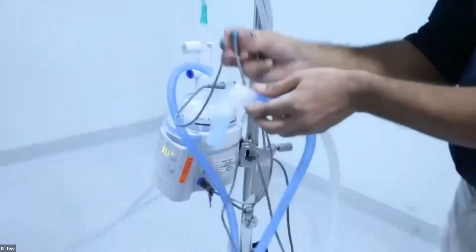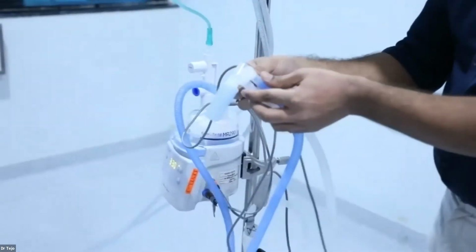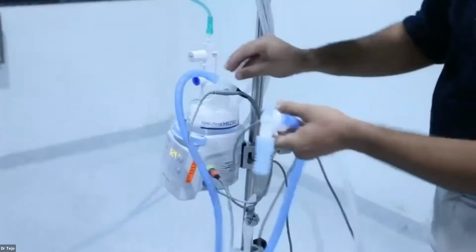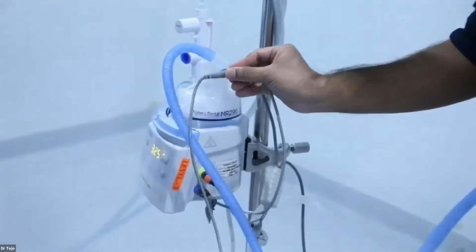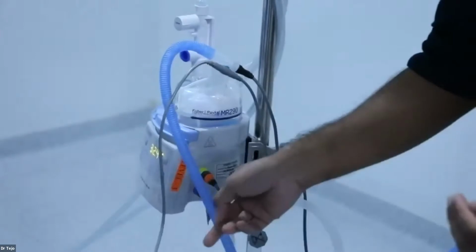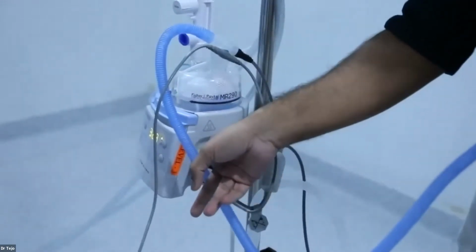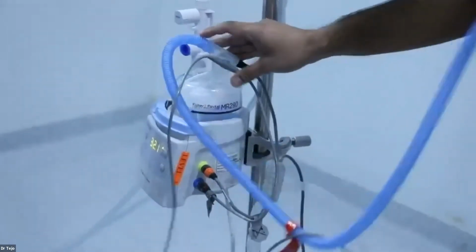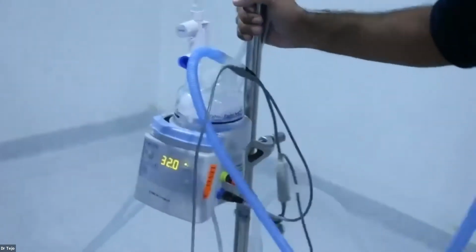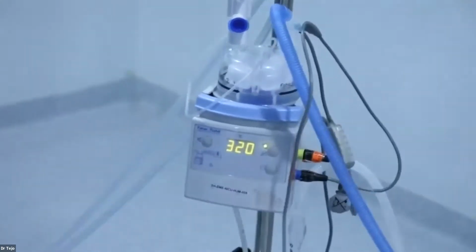This is the airway probe which we are connecting at the patient end, and this is a chamber probe which we are connecting at the chamber exit, and this is the temperature probe which is sensing and giving to the humidifier. So these are the parts of the humidifier. Okay. So coming to the alarms of the humidifier.